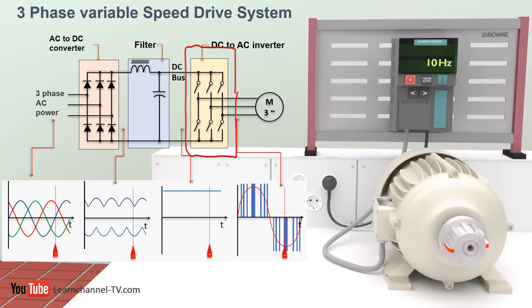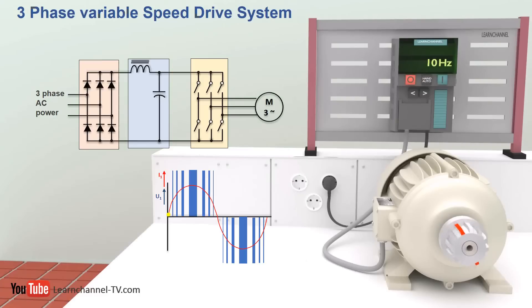The filtered DC bus voltage passes through to a DC to three-phase AC converter. The DC-AC converter consists of an array of fast-acting switches which convert the DC voltage into voltage pulses of square shape, constant magnitude with varying width.